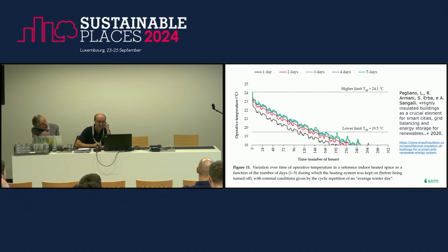If we keep the heating on for two days instead, we get the red curve, and the simulation shows we stay in comfort for five days without any energy input at all, and so on for a charge phase of three days. So with one or two days of charging the building we get a comfort autonomy of three to five days; we don't need to charge for five days, since we've already saturated the thermal capacity of the building in a couple of days.